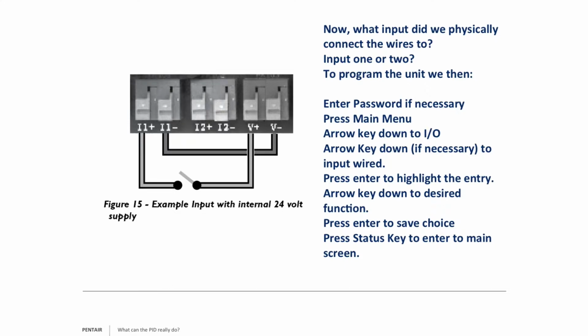So you look at the screen, if you see the little skeleton key or the Franklin key in the corner, that little icon tells you the unit's locked. If that's the case, you enter in your password. Remember, the password default is 7777, four sevens. Then go into main menu. So hit the password key, put in your password, enter, then press the main key. Then you're going to arrow key up or down until you get to I/O, which is inputs and outputs.